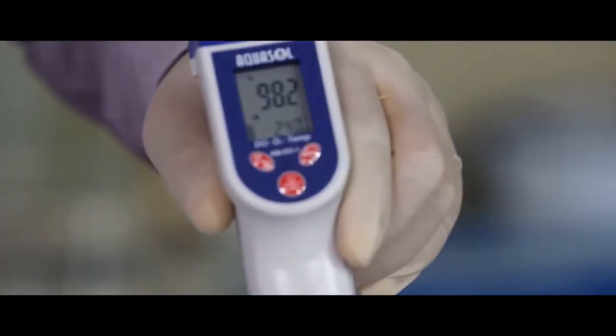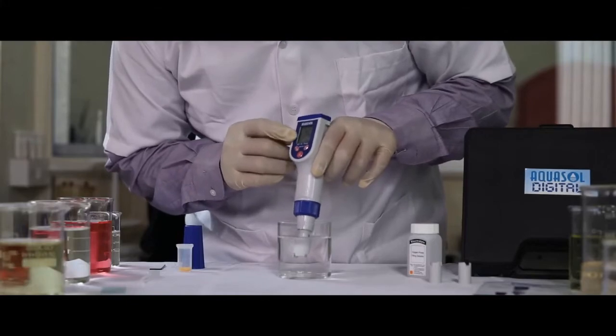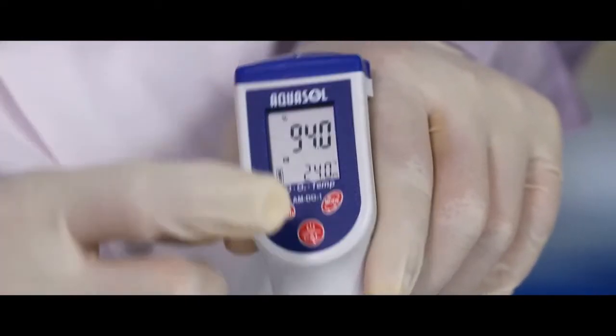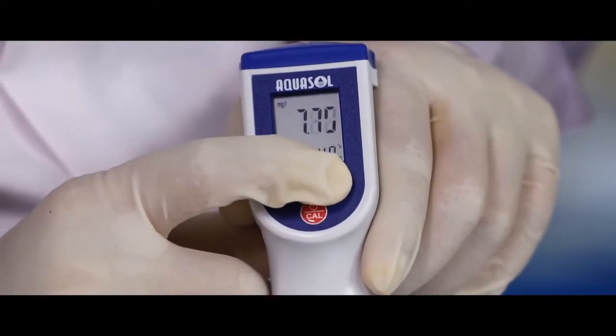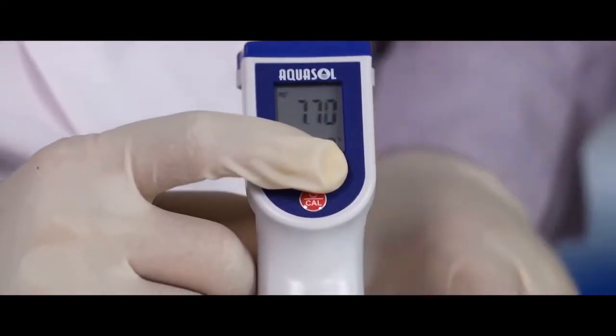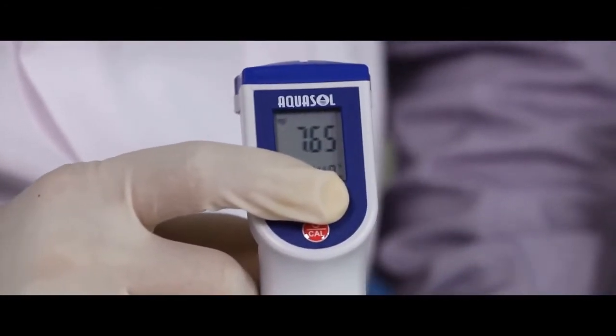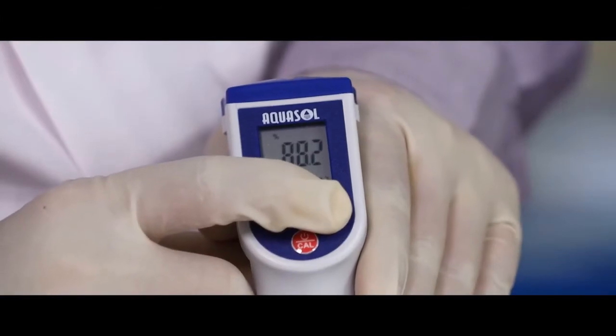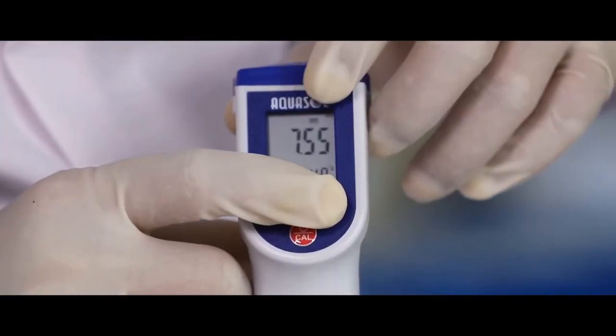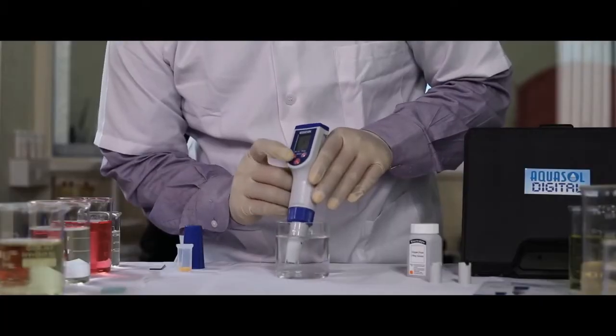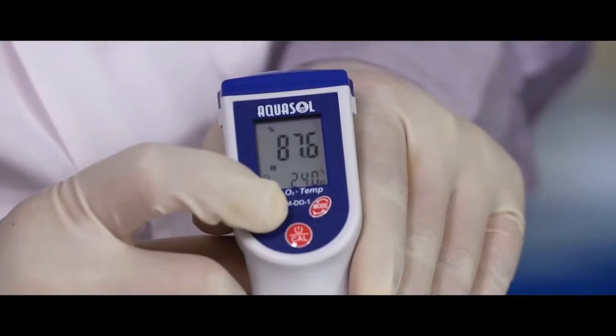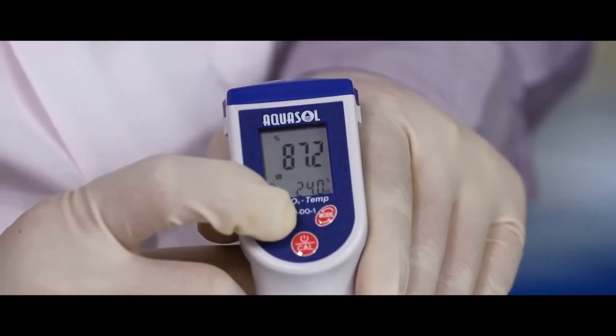Stir the electrode till the reading stabilizes. You can see the O2 value and percentage on the display. Press mode to find the DO of the sample in different values like milligram per liter, percentage and PPM. Press H/M key to hold the reading.